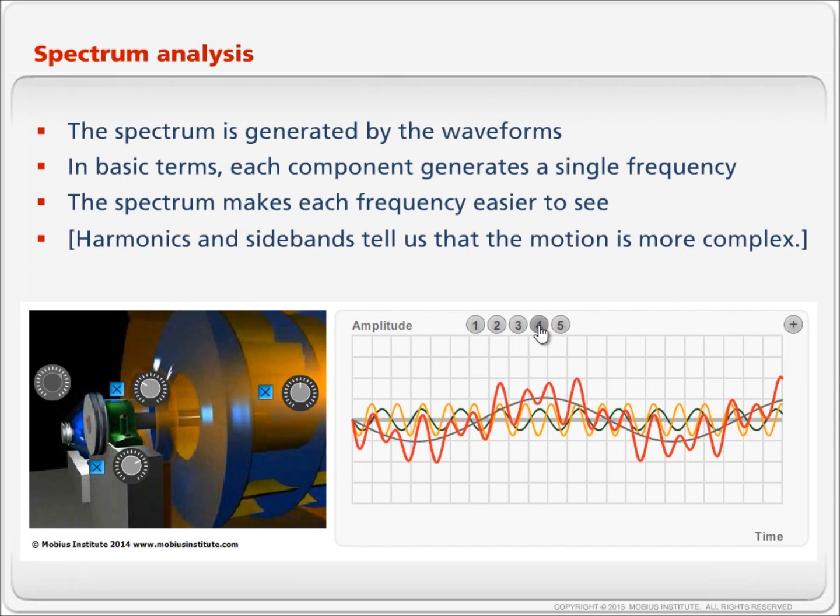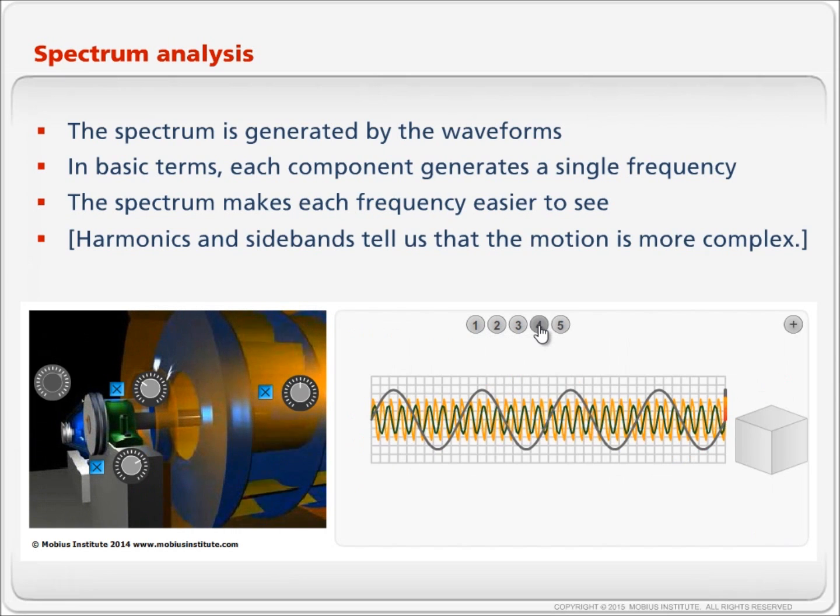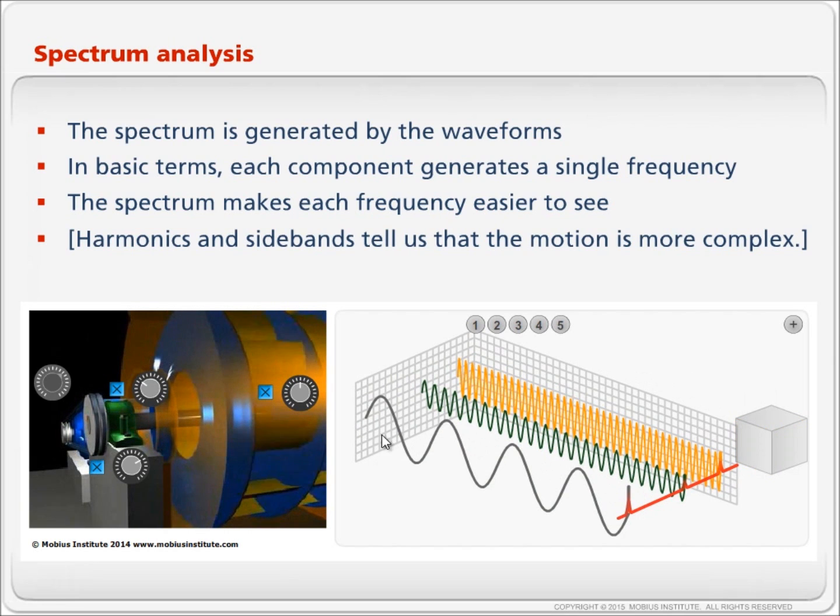Let's look at this in 3D. What we're seeing here is basically what we saw before. There is the grey vibration, the green vibration and the orange vibration. Now I'm going to rotate our view. This is the passage of time, this is amplitude. But we've got a three dimensional picture because now we have separated the three waveforms in terms of frequency. The shaft turning is a lower frequency, higher frequency is the green vibration from the bearing, and the orange vibration from the fan is higher frequency still.